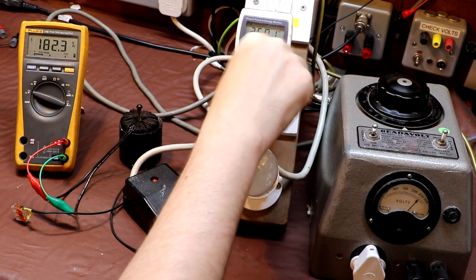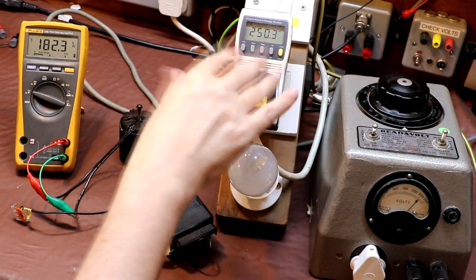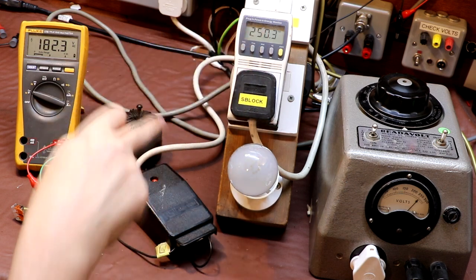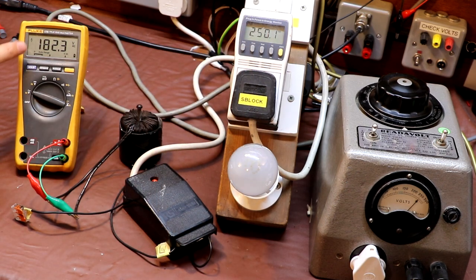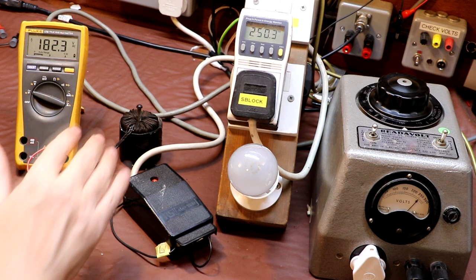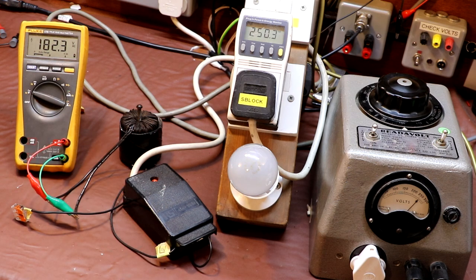Okay, 250.1. So we've got 250.3 volts going into our transformer now, and looking at the secondary voltage, we've got 182 volts coming out of it, and the transformer's off load. We've got no load connected to the secondary.